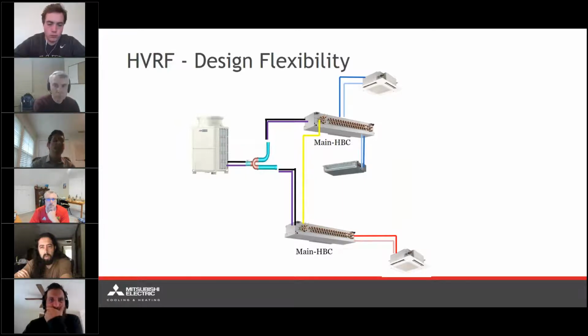So one of the limiting factors for the size of a VRF system is how far away the furthest fan coil is allowed to be from your BC controller. Well, for this particular instance, having a second main BC on a system, we don't need to worry about the distance from the primary or the first HBC. We can use the secondary main BC as a new datum point to ultimately expand the distance that all the fan coils could be apart from each other.